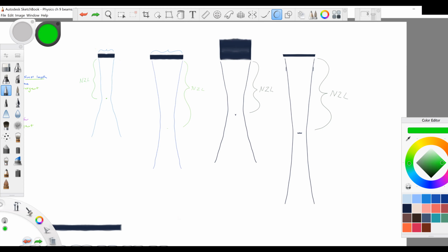If on the other hand, you have to use a low frequency transducer and you want the natural focus to be deeper, well then you have to use an element of that thickness to create the low frequencies, but you also have a large diameter transducer, and hopefully you can create a natural focus which is appropriate for your needs.